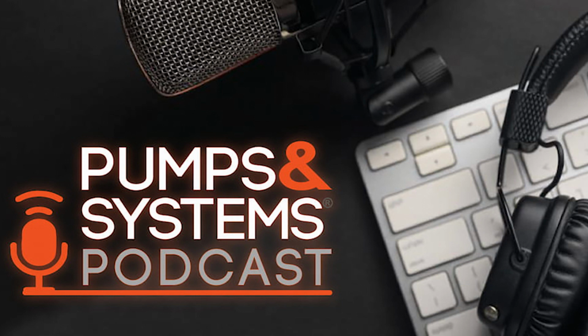Bill, we're going to talk about seal water on this podcast. What is seal water? Seal water is simply used as a lubricant or barrier fluid to cool and keep the faces clean. Think of a mechanical seal as basically a bearing, in that you've got a stationary and a rotating part. If we call them seal faces, if they're not kept cool and clean, they're going to wear out very quickly, just like a bearing. And so a seal water flush is what the primary function of that is.